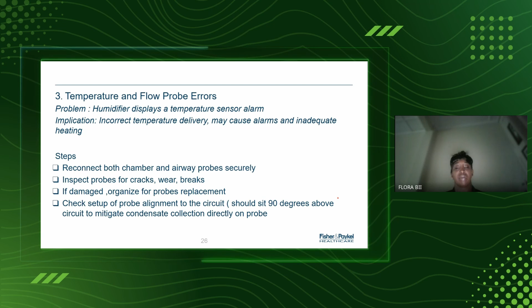So in terms of positioning of the circuits and the temperature probes, you would check that it actually latches. These probes do have different designs, so you would check that it has been fully pushed in on both sides, on the humidification chamber as well as in the circuit itself, just checking that it is in the right places.